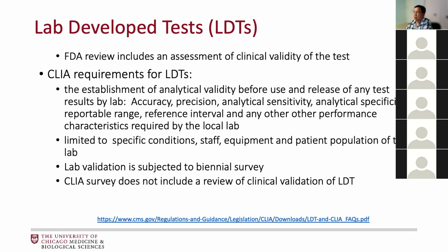All right. So in terms of CLIA requirement for LDT, we just have to establish that it's analytically valid. That means it needs to be accurate, precise. You got to define how low you can measure whatever you are claiming to measure. You have to define that your test is measuring PSA and not cross-reacting with something that looks like PSA. So you want to make sure that it's specific. You have to define what is the reportable range. If it's a quantitative test, you have to provide some sort of a reference interval, meaning what normal people would run.